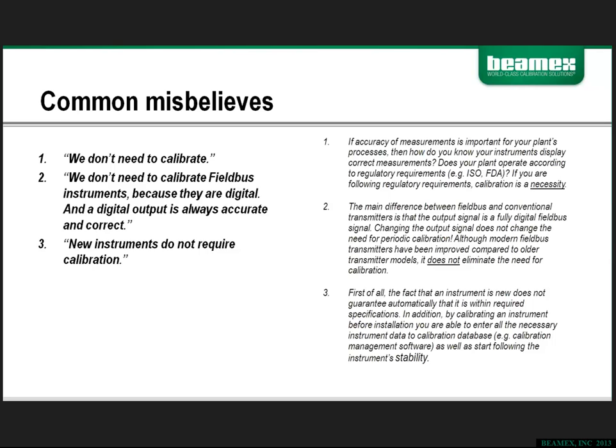So, number one, we don't need to calibrate. In order to achieve the desired result of your manufacturing process, in the end, which is a quality product, you must first know that the process itself is occurring in the way in which it was engineered. Calibration validates this through measurement and comparison of those results.